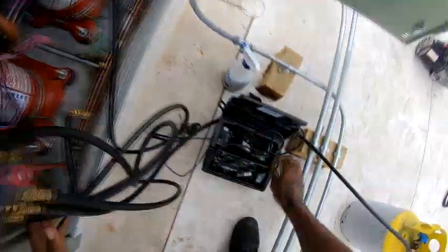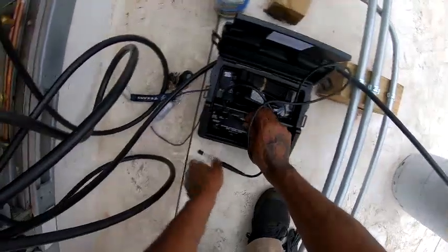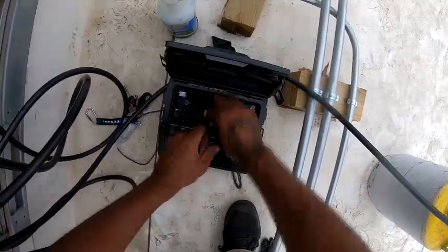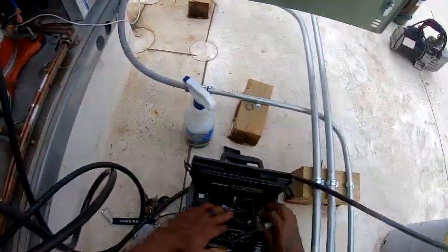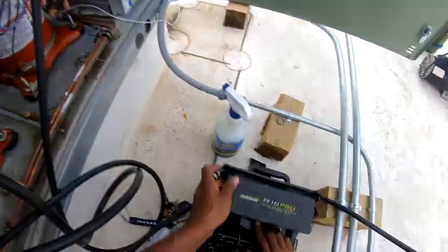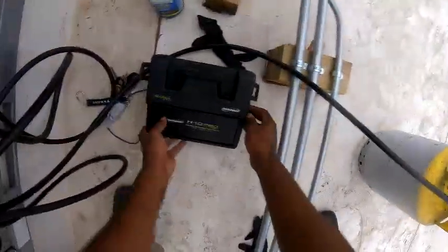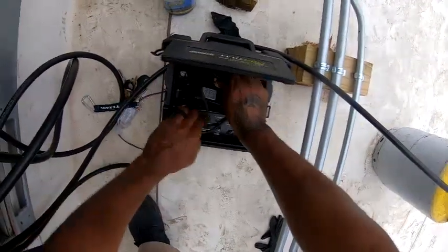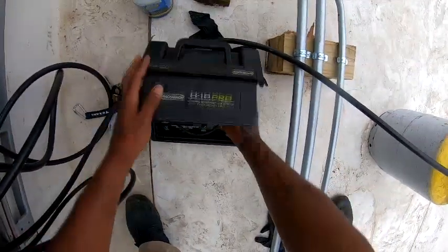Let's see if we can leak out some of this gas. I'm gonna leave a little bit in there and see if we can get some big bubbles, try to get it down to about 5 psi, then put some Snoop on there and see if we found the leak. That's why instead of using all your nitrogen up, it's good sometimes to just put a little bit in there, just barely crack the nitrogen bottle, put about 5 or 10 psi, and you can find a leak. It don't take much.